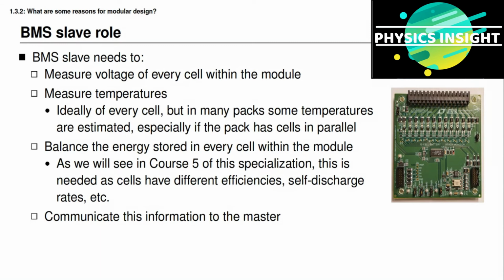The particular solution shown here uses a serial bus where the master can communicate over a daisy chain bus to the individual addressable components, or to all of them at the same time using a broadcast message. The connectors that allow this are shown at the bottom, to the left and right of the board, where one side connects from the neighboring board into this one, and the other side connects out to the next neighbor, with one finally connecting to the master unit.